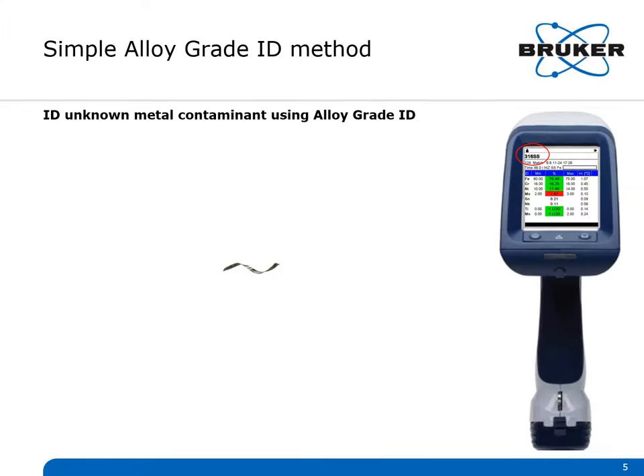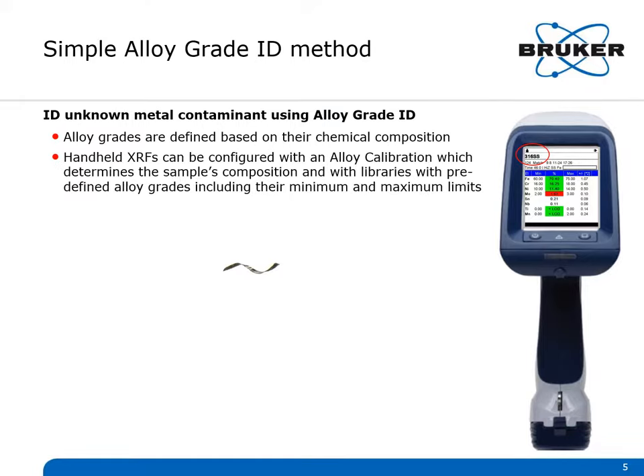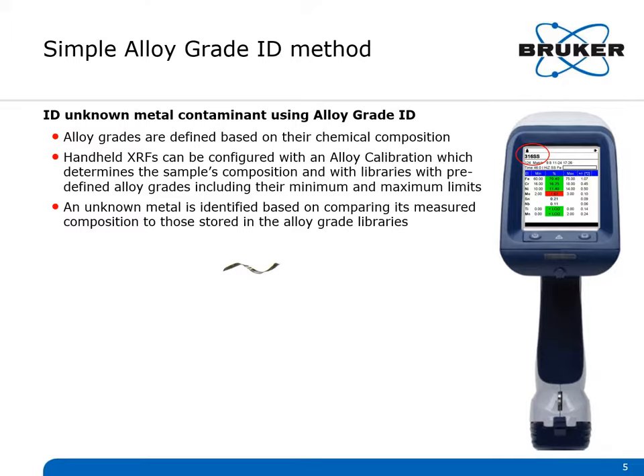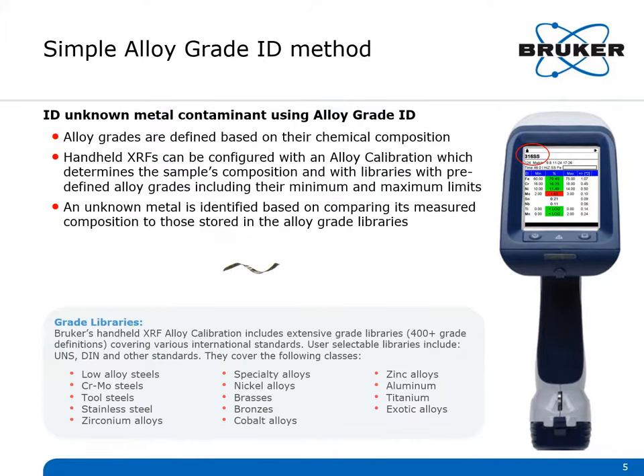XRF identifies a metal contaminant's alloy grade because alloy grades are defined based on their chemical composition — which elements they contain and at what concentrations. Handheld XRFs can be configured with an alloy calibration that determines the sample's composition and has libraries with predefined alloy grades, including their minimum and maximum limits. The grade libraries are extensive, covering hundreds of grade definitions across multiple international standards including UNS, DIN numbers, and other standards, as well as multiple classes of alloys.